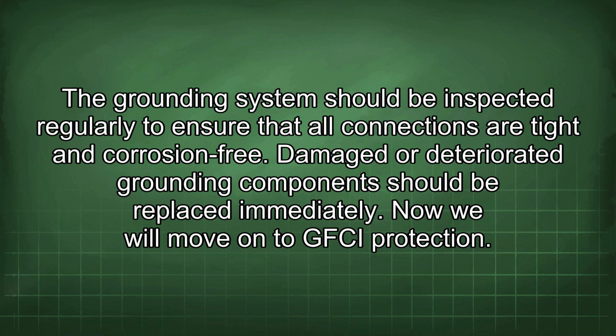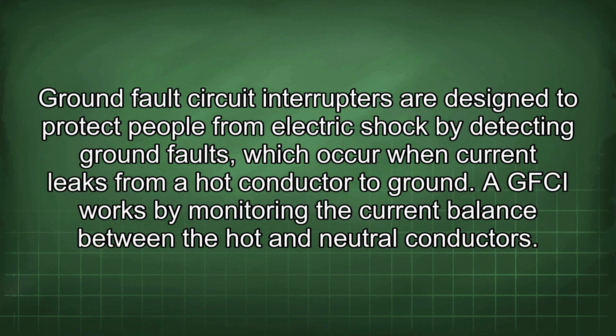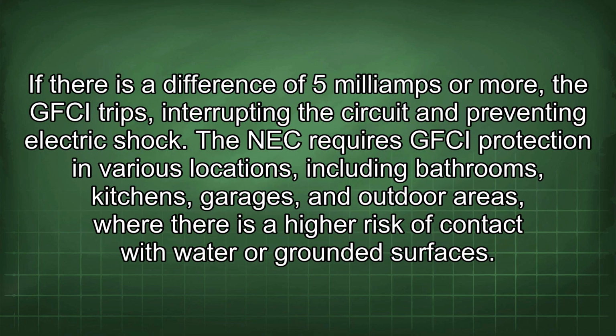Now we will move on to GFCI protection. Ground fault circuit interrupters are designed to protect people from electric shock by detecting ground faults, which occur when current leaks from a hot conductor to ground. A GFCI works by monitoring the current balance between the hot and neutral conductors. If there is a difference of 5 mA or more, the GFCI trips, interrupting the circuit and preventing electric shock.